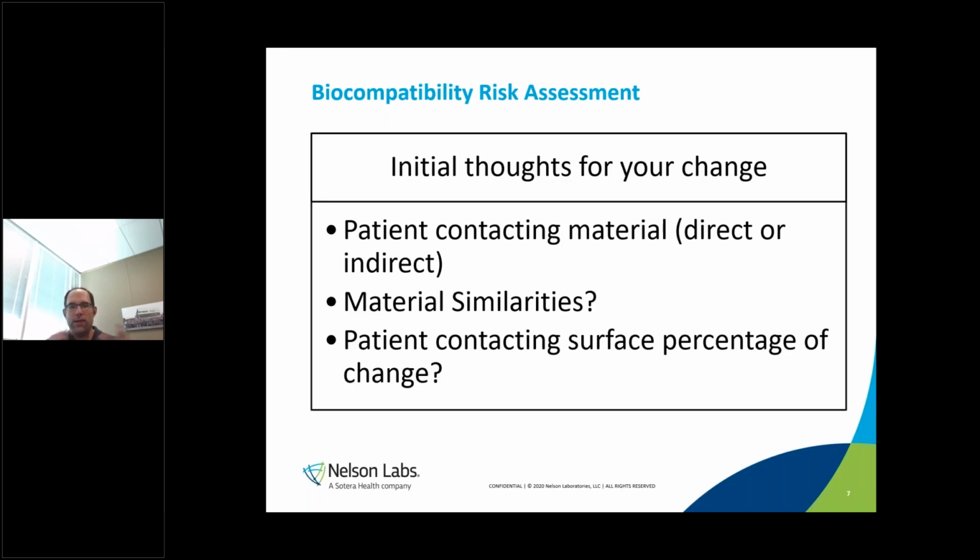And so you can have a device that you've tested biocompatibility, you've done extractables and leachables on, it has tox assessments, you've gone the whole way, and it's approved on the market. And now you're thinking about adding length to that device, or maybe you are increasing the colorants that you already have on there, or maybe you're now adding more of a coating or something along those lines. Remember, it's about dose. And so even though you're using the same materials, same processing, things like that, you're now increasing the dose of a certain material. We have to evaluate that as a potential risk.